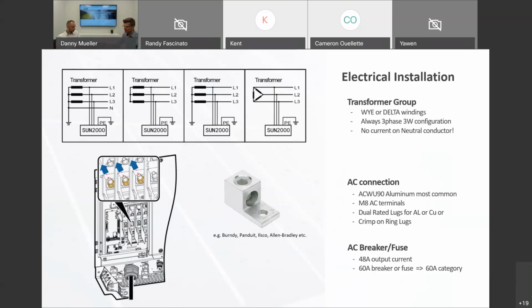And when we look into the design of the system, the output current of the inverter is actually 48.0 amps, which means with the sizing factors we have here in Canada or in the US, we can use exactly a 60 amp breaker or fuse to make that happen. Which is also a good thing if you have requirements that adjacent to the inverter, there has to be a disconnect switch on the AC. Some jurisdictions have that, some jurisdictions don't. You can stick with a standard off-the-shelf 60 amp size switch without having to upsize it to 100 amps, even though you're only using it at slightly over 48 amps in other systems.